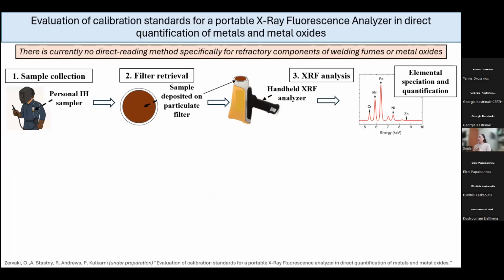Basically, what we wanted to achieve was, let's say there is a welder in the field doing their shift. They use a personal sampler where the aerosol sample is collected on a 37 mm filter. And after the 8-hour shift, for example, we can get the filter. And right then and there, we use a handheld XRF analyzer to quantify and specify the elements, the metals, that the welder is exposed to. And we get the results right then and there with no sample preparation, without having to wait for days to get the result. So we can get instant and fast decisions.